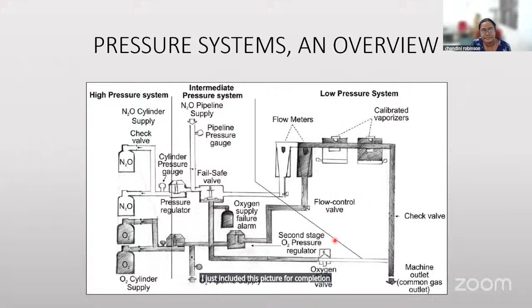Now, commonly encountered problems with a Boyle's machine. Boyle's machines are to be used with a high degree of vigilance. Vigilance is required from the moment the cylinder is attached to the machine. Although there is a pin index safety system, and a diameter index safety system if pipeline connections are available, there is a propensity for a wrongful connection. So a manual check has to be ensured before, and we also need to ensure the availability of proper pressure and proper gas flow in the cylinder.